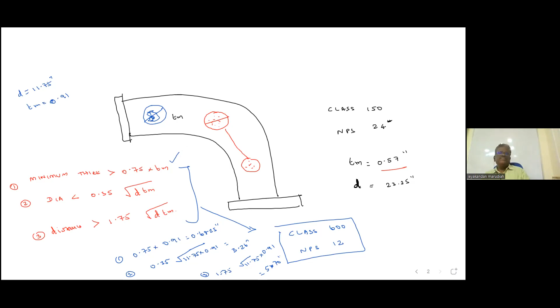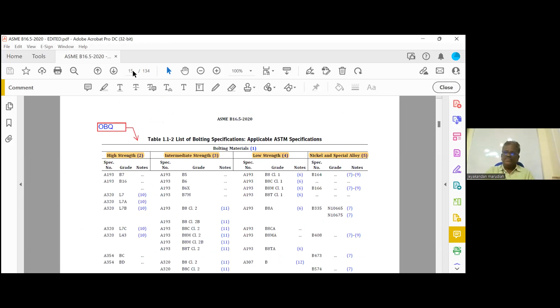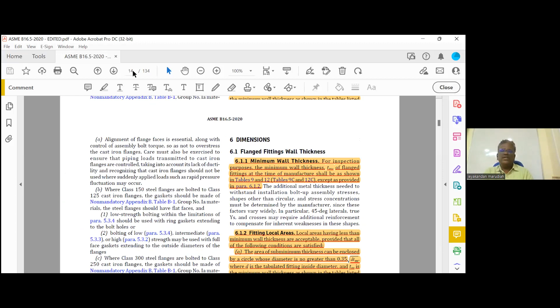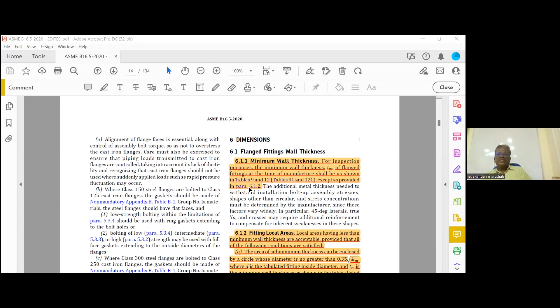Right. So back to the original page. Fitting in local areas, page number 8. For inspection purpose, the minimum wall thickness TM of flanged fittings at the time of manufacture shall be as in tables 9C to 12C. Local areas having less than the minimum wall thickness are acceptable provided all of the following conditions are satisfied. A, the area of subminimum thickness can be enclosed by a circle whose diameter is no greater than 0.35 square root of DTM, where D is the tabulated fitting inside diameter and TM is the minimum wall thickness. B, measured thickness is not less than 0.75 TM. C, enclosure circles are separated from each other by an edge to edge distance of more than 1.75 square root of DTM. If all three conditions are met, the fitting can be accepted. Just mark it, not very important.